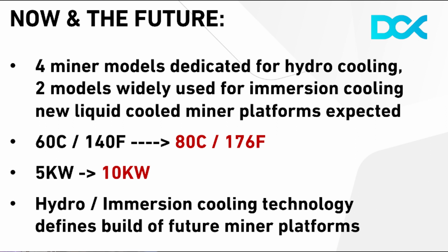Which is 176 Fahrenheit, which is a lot. And you should expect 10 kilowatts. So we can assume that future miners will actually be defined by liquid cooling technology. There will be no future miners at that power level which are air cooled. That's not possible physically. And the fact is that liquid cooling technology has been known for decades.